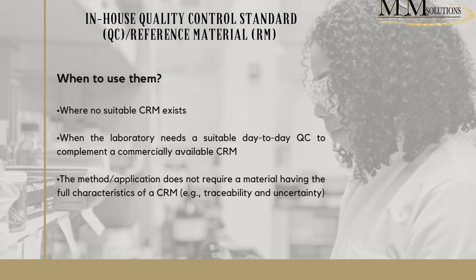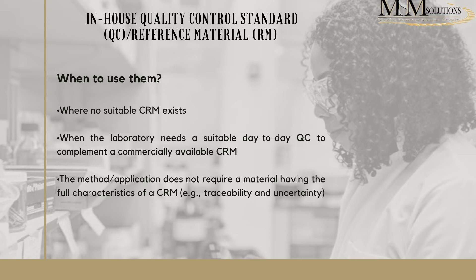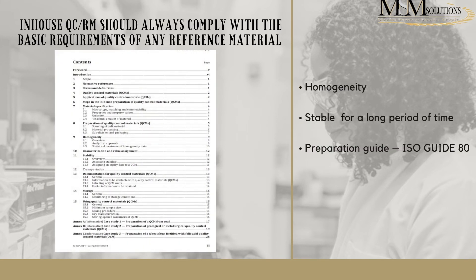However, you still need to make sure that it fits the description and does what it's supposed to do — meaning it must still be homogeneous and stable for a long period of time. There is a preparation guide, ISO Guide 80, which can help you prepare this material to make sure that even if you're using it internally, you still prepare it in the best possible way. This guide would be used by reference material producers, but you can internally use it for your own in-house QC material to ensure stability and homogeneity.